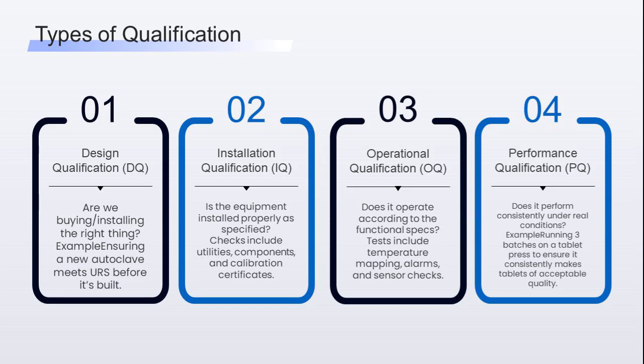For example, you are ordering a new autoclave. DQ ensures it meets the URS — user requirement specification — before it's built. IQ, installation qualification: is the equipment installed properly as per specifications? Checks include utilities, electrical, water, air, components, part numbers, and calibration certificates.